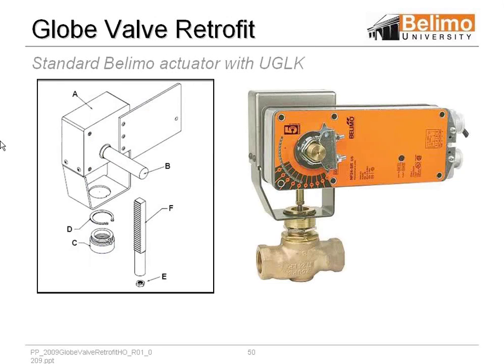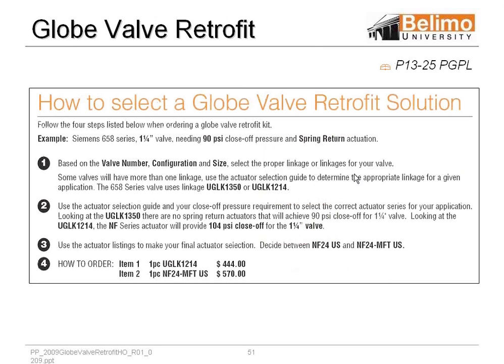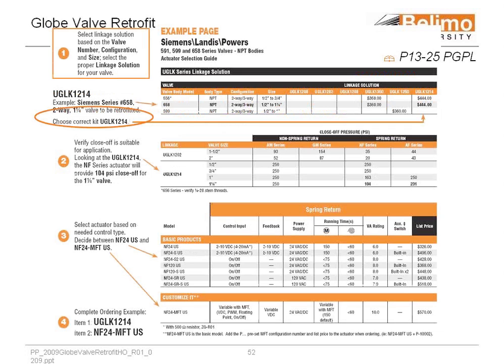This is just a quick picture of a kit, a UGLK kit with the NF actuator on it. So how do we pick a UGLK kit? This particular example, we need a one and a quarter inch valve, needing it 90 pounds close off spring return. So based on those numbers, we go right to the actuator and here we have to pick out a UGLK kit.